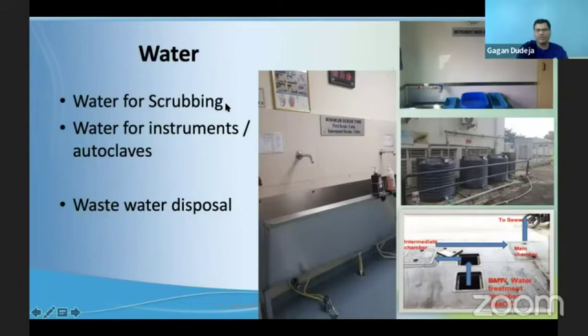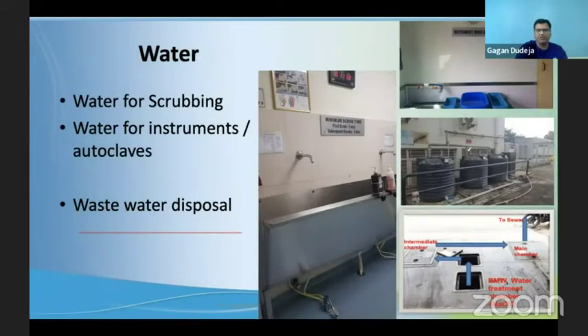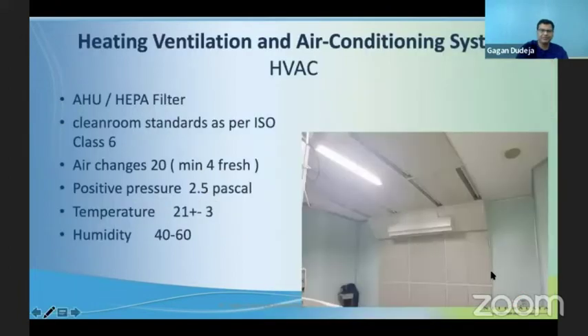Water is needed for scrubbing and instrumentation. Most important, with the new biomedical act, is water waste disposal—you have to treat the water from your OT before you dispose of it. You need tanks to pre-treat it with sodium hypochlorite. This was a retrofit solution since the act changed late, requiring external tanks, but now you can actually have the tanks underground serving the same purpose.